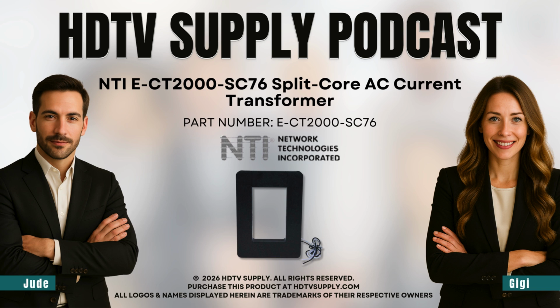Let's talk about the data. It's measuring this huge 2,000 amp current, but the output is 333 millivolts. That seems incredibly small—what's the logic there? It's standardization. That 333 millivolt output is essentially the global standard for industrial sensors like this, so it talks to almost any SCADA system, any data logger, any controller right out of the box. It steps that huge dangerous current down to a clean, safe, and universal signal, making integration almost effortless.